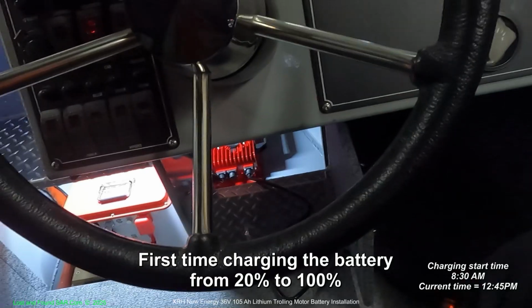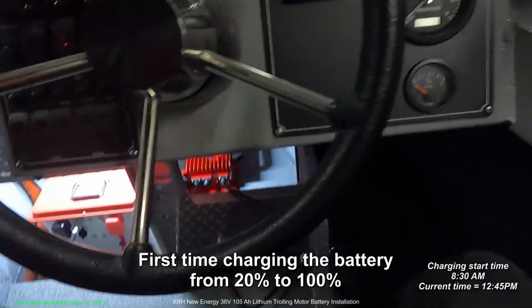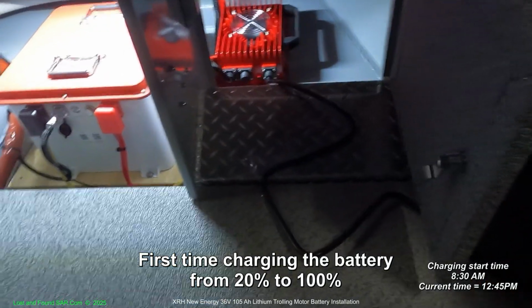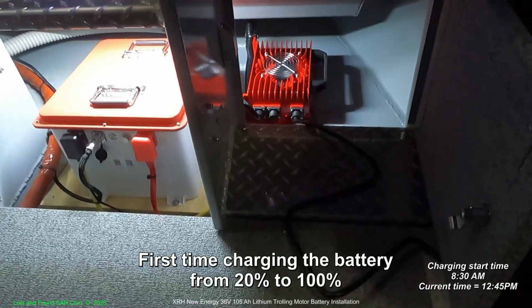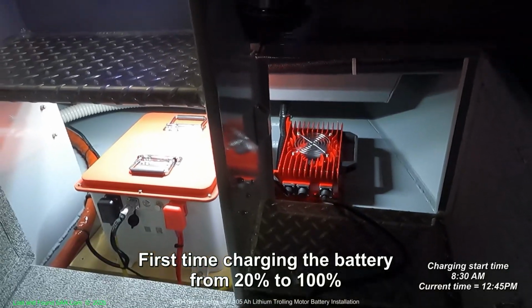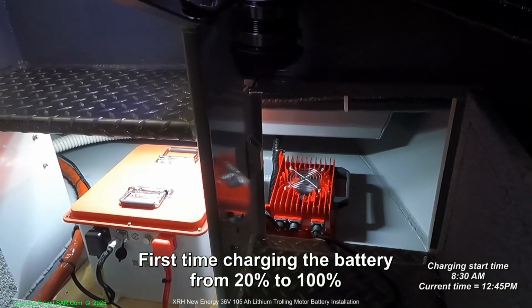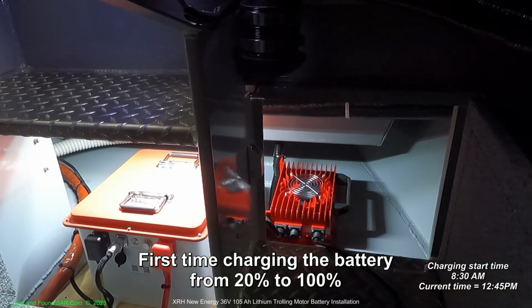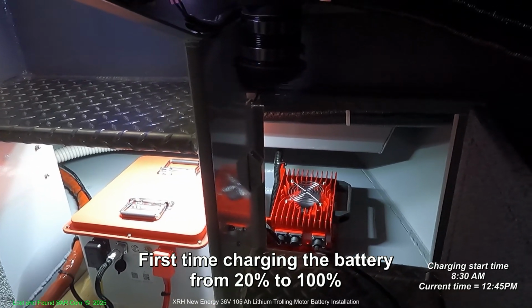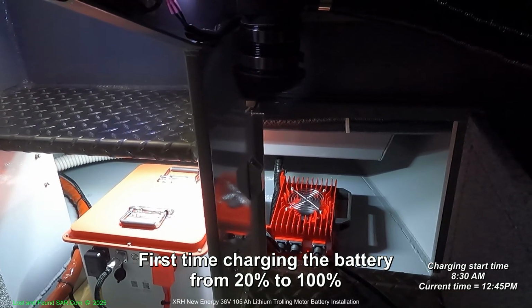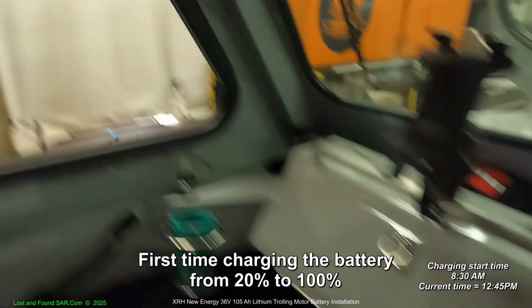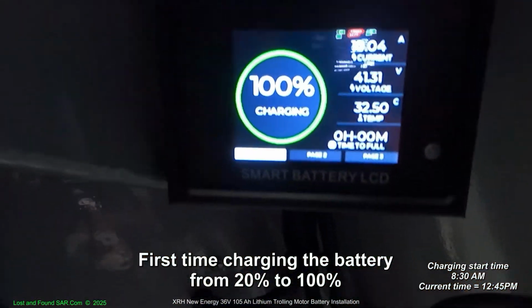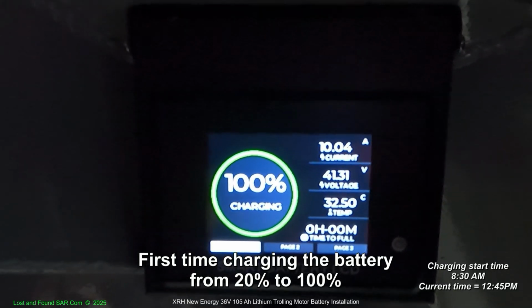Let's see if it says anything about charger. Battery charger: estimated charging voltage between 43.6 to 43.8. So that's what we should be getting on that BMS meter then? Something between 43 and 46? That's what it says, 43 and 46, 43.6 to 43.8. Well, it's going up. It's 41.31 right now.